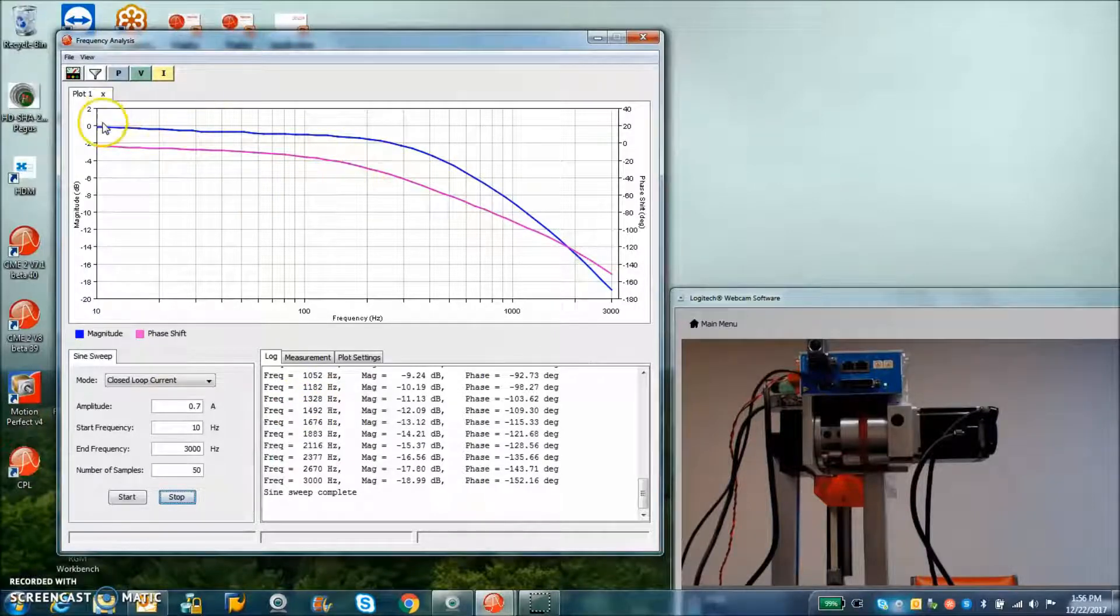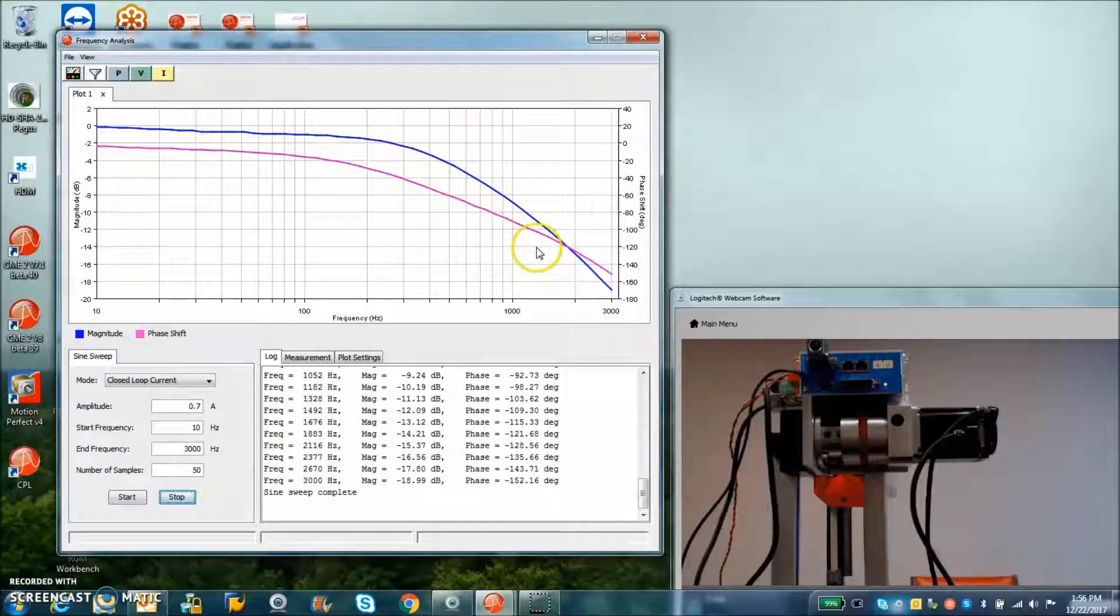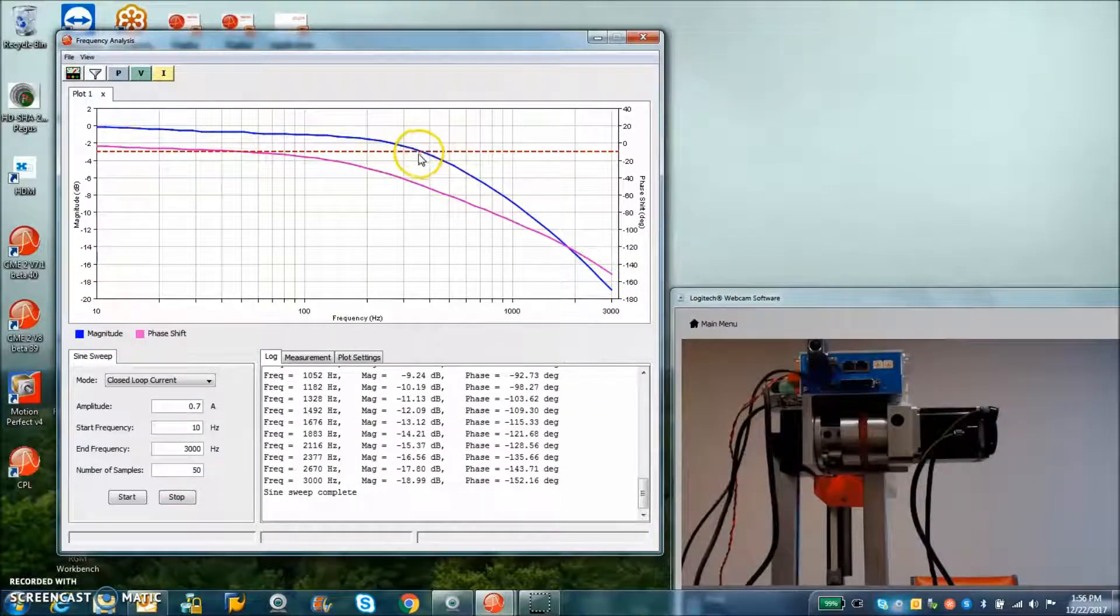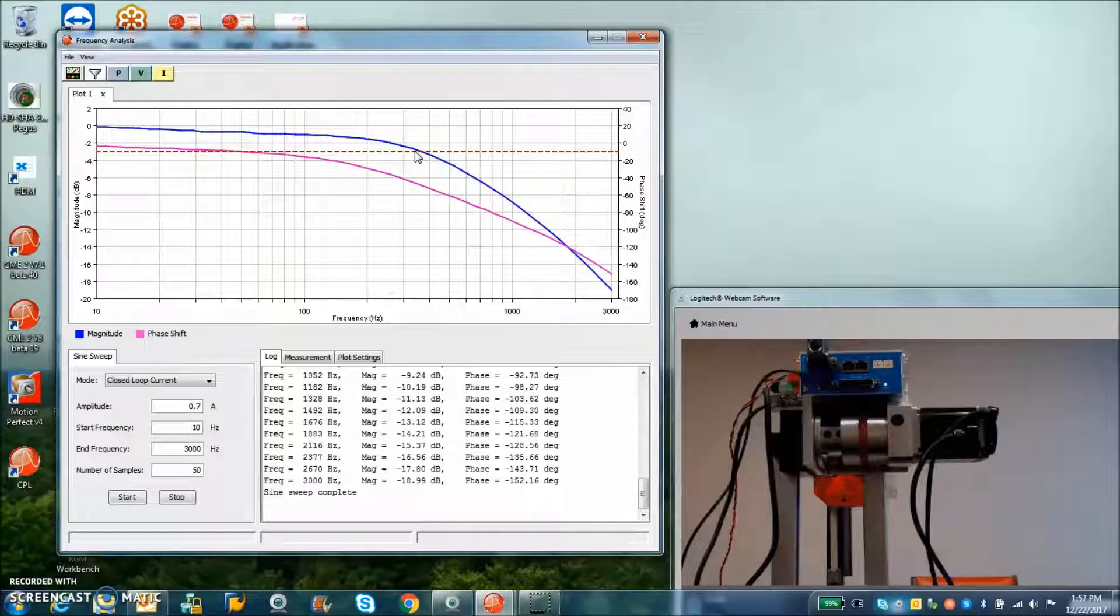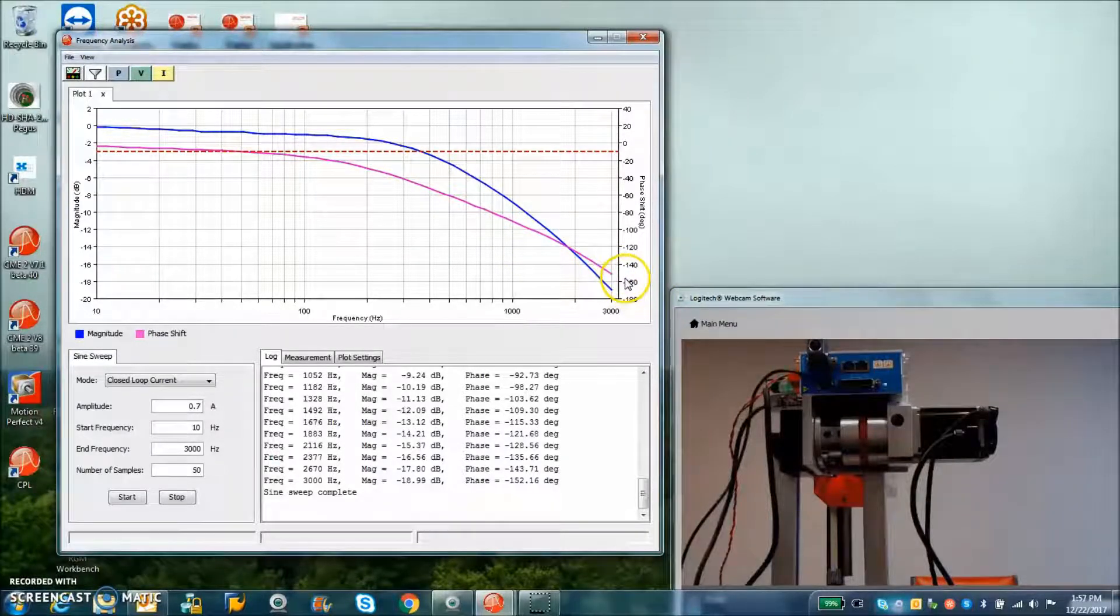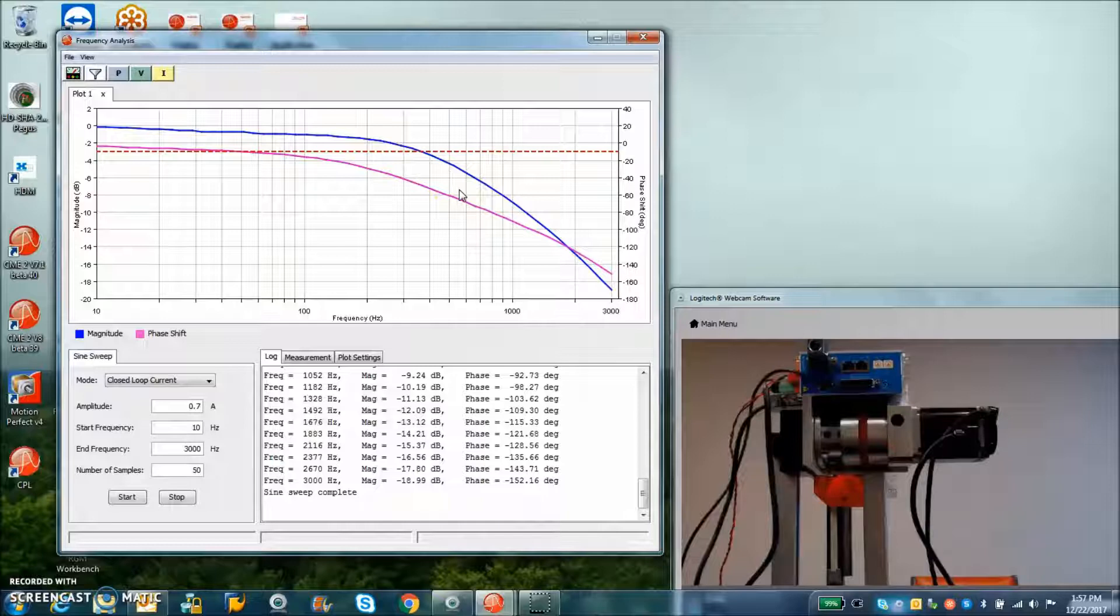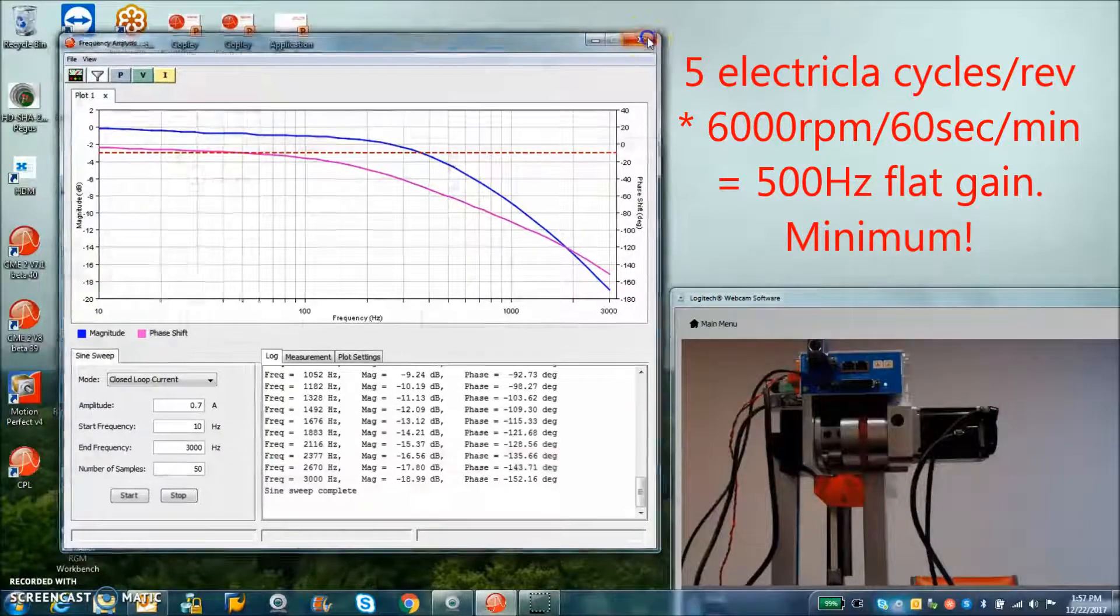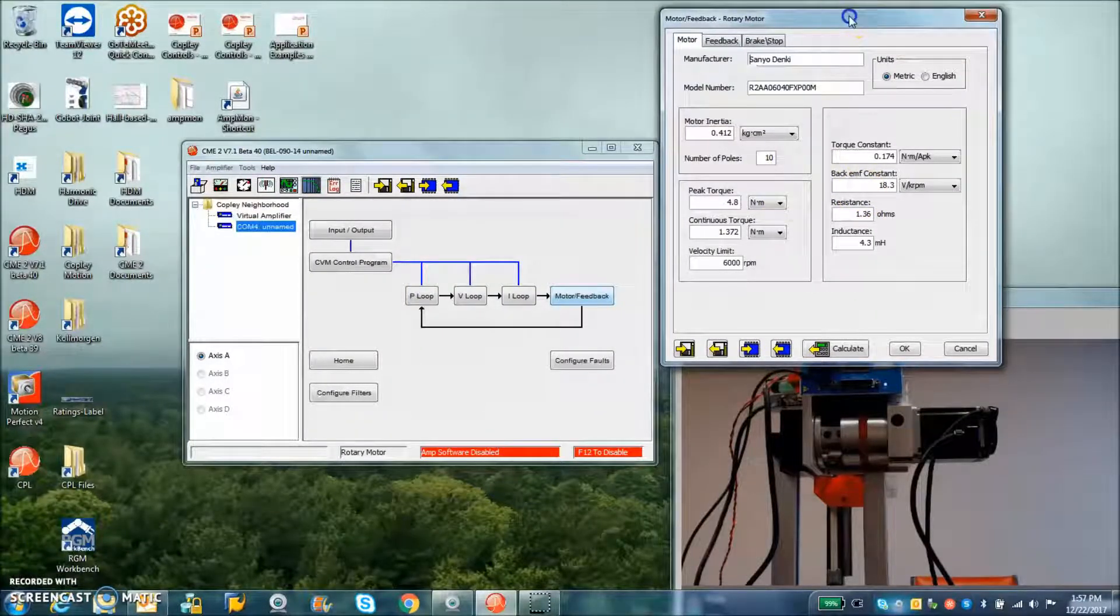So you can see that the gains of the current loop is flat and it goes out and then starts to roll off. We've got a minus 3 dB point here at about 1,2,3, 400 hertz. That's a little sluggish. I like about a kilohertz of current loop bandwidth and then the phase starts at zero and rolls off. Had we gone further you could see where the phase shift was 180 degrees. So lots of gain margin, lots of phase margin here. You know phase of zero, gain of one and you got a resonator. So you got to stay away from that. But we're going to take a look at what we did here to get this current loop and then we'll investigate the velocity loops after that.